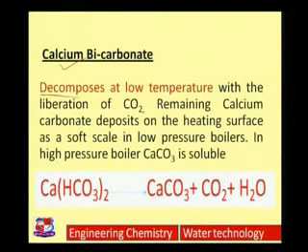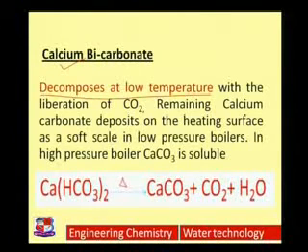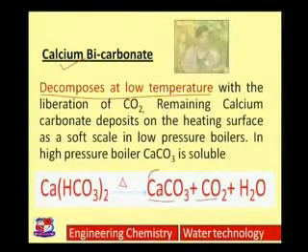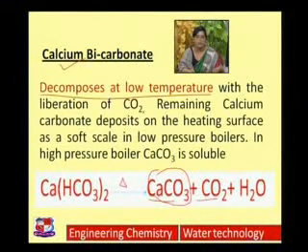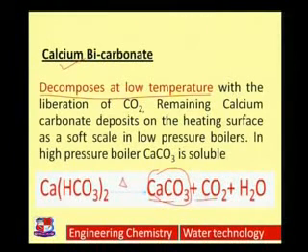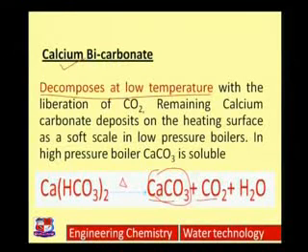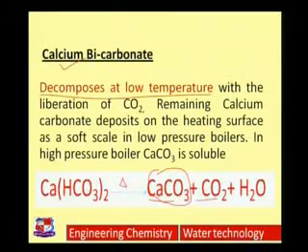Calcium bicarbonate decomposes at lower temperature in the boiler — upon heating, calcium bicarbonate gives calcium carbonate, carbon dioxide, and water. This calcium carbonate acts as a scale. It is insoluble and acts as a scale in low-pressure boilers. In high-pressure boilers, CaCO3 is also soluble and does not act as a scale. So scales are adherent thick precipitates deposited on the inner walls of the boiler, caused by presence of silica, hydrolysis of magnesium salts, calcium sulphate, and calcium bicarbonate.